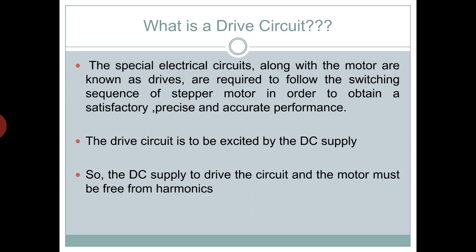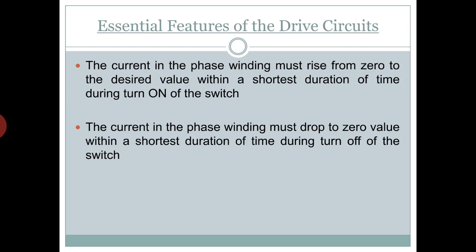The drive circuit is also excited by the DC supply, so the DC supply to the drive circuit and motor must be free from harmonics as much as possible in order to obtain precise performance. The single phase rectifiers contain harmonics and irregularities, so they cannot be recommended for this purpose. Batteries or three phase rectifiers are best suited for these applications as they are free from harmonics.